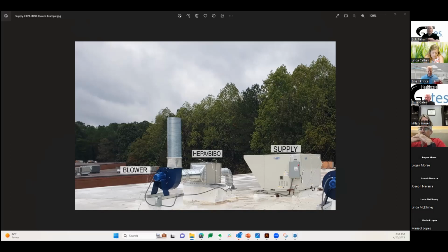You can build a room anticipating adding more stuff two years down the road. And if it's a hazardous room, for those two years you're going to be throwing a vast amount of money out because of the size. But the second thing is, is that equipment capable of handling it? Well, maybe not. Fan curves and all sorts of stuff come into it. So you can design it to be big enough to handle it in the future with a hot gas bypass to throw artificial heat in, which is horribly expensive. So you can do it, it's not a great idea, but it's as simple as that.